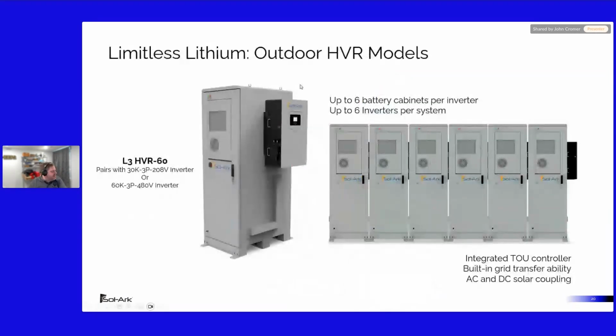We'll get to your question, Jerry, in a moment. So we have 208 volt products and we have 480 volt products. The question is, what about Delta high leg systems? That gets a little confusing, because 480 volt Delta is not Delta high leg. With the 480 volt system, it'll work with Delta or Y. With 208 volt, when you go to Delta high leg, that's often a 240 volt three phase where one of the legs has a little bit higher voltage, and for that you're going to need an external transformer. We only support 208 volt Y without an external transformer for the L3 series.